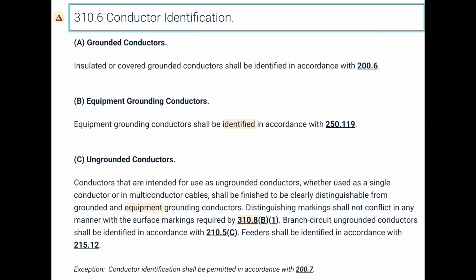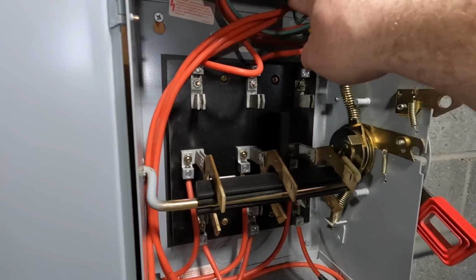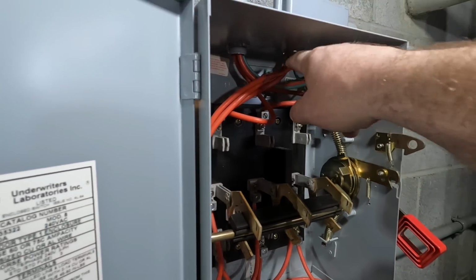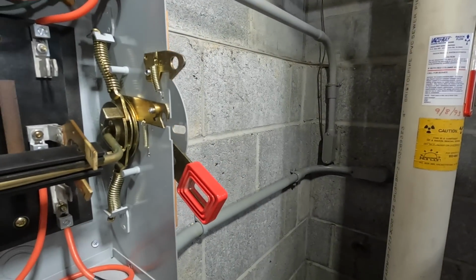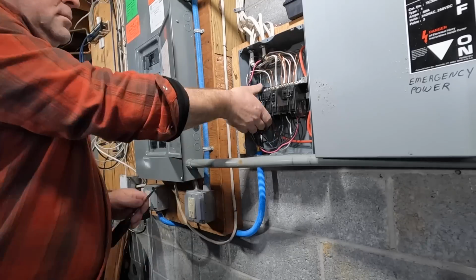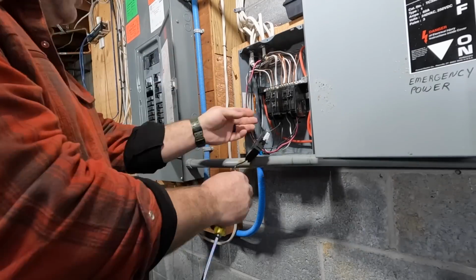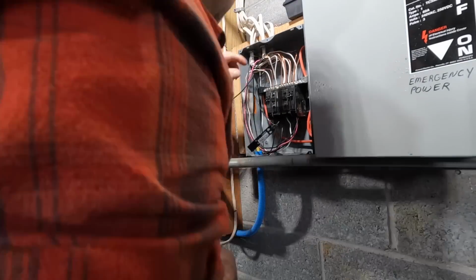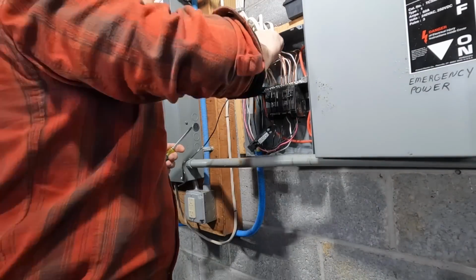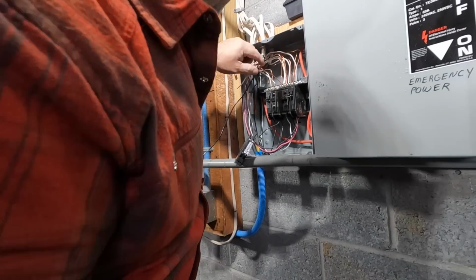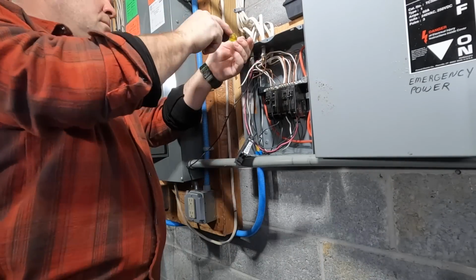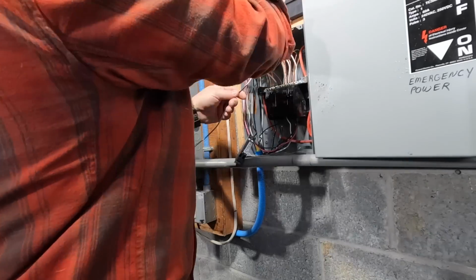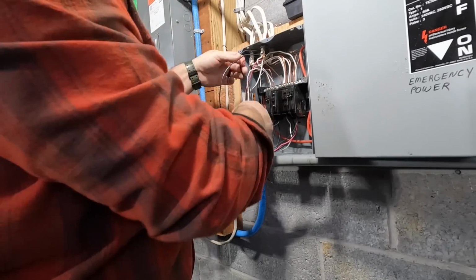This section of the code shows you what color the conductors need to be: grounded, equipment grounding conductors, and ungrounded conductors. Hit pause if you'd like to read more on this section. And I believe this goes out to the old generator hookup on the outside that goes underground. We're going to be disconnecting all that. So I normally wouldn't do this, but what I'm doing here is obviously taking out all of these circuits to go inside the new main breaker panel. But I'm going to isolate the boiler circuit, and I'm going to temporarily connect it to an extension cord just so that we can have heat, because it's 10 degrees outside on this day that we're doing the work.